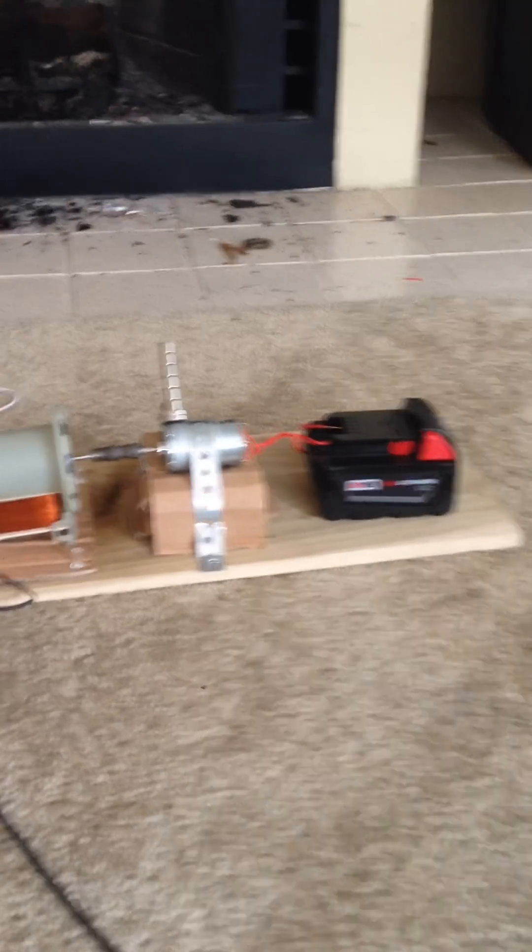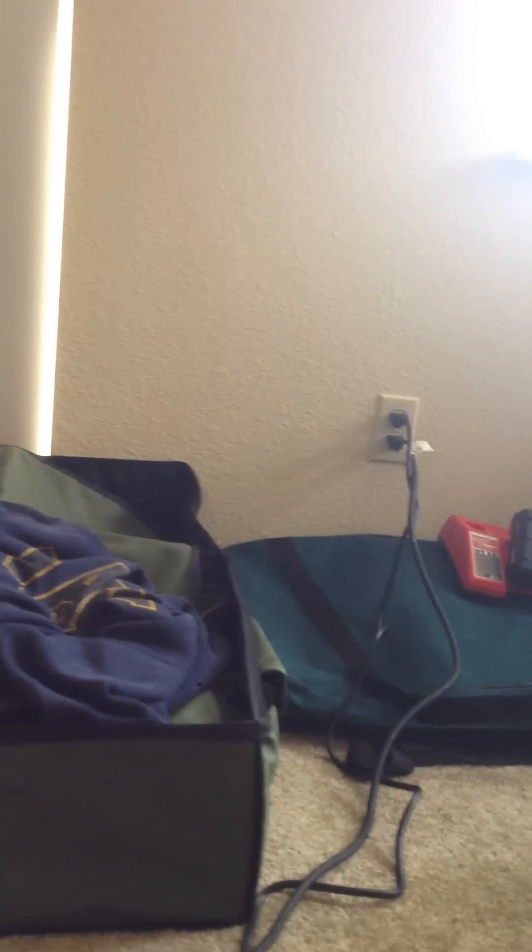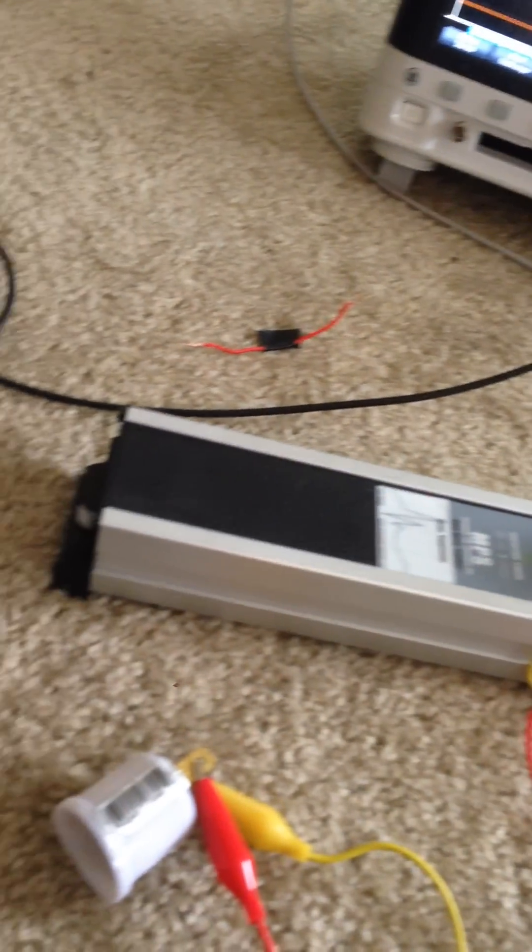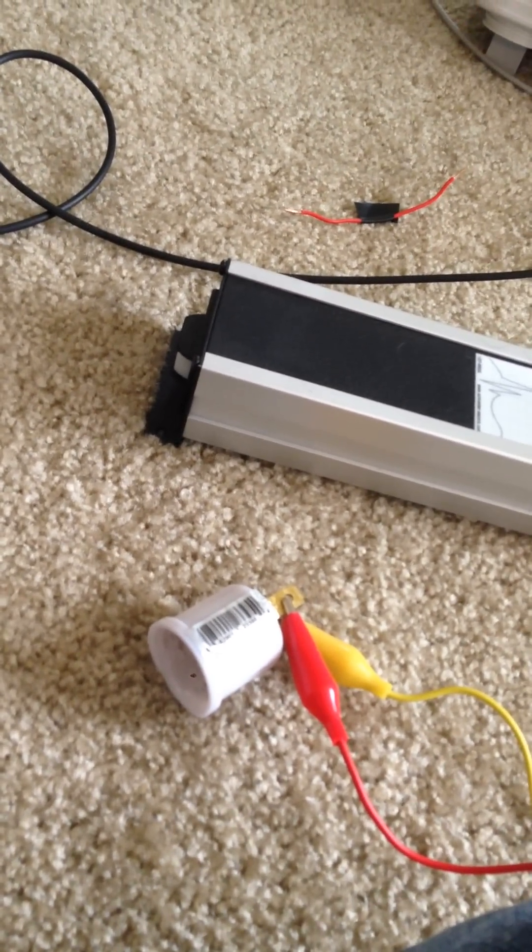Alright, so what I'm trying to accomplish in this video and show the rest of the community is that what's coming out of the wall is not what's coming out of this induction pump. And what do I mean by that? I mean the waveform. I'm going to show you that what's coming out of the wall, right? Follow this here. Sorry if you're getting seasick with all the camera moving around. Right here is where we're going to check it. I'm going to check the waveform. I'm going to check it with two different loads.